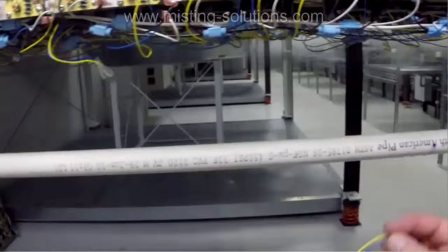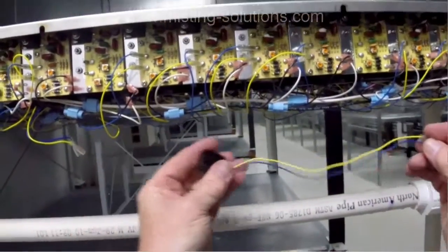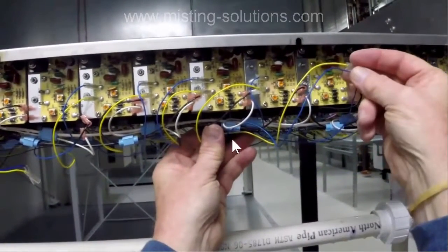I'm going to back up here just a bit. Let's see if I can do this. There, watch this. Right there. So you can see that transducer goes in right there, but then the actual leads go to this guy over here, or maybe even this guy over here, and you couldn't do it with the shorter ones. So 2/3 of the unit use short leads. The last third towards the front where the power strip is uses longer leads. Now there's a couple of exceptions in there that you'll see, but that's generally the idea. Boards start to get further down the unit than the transducers, and you've got to use longer leads.